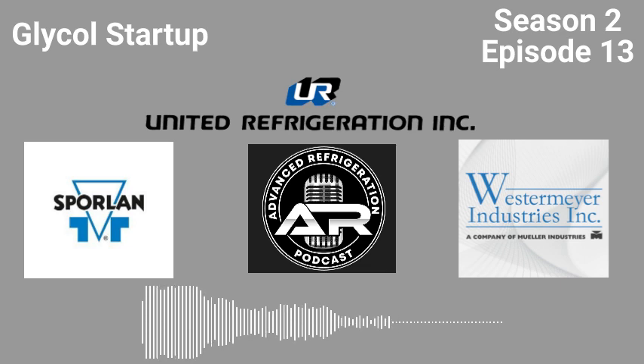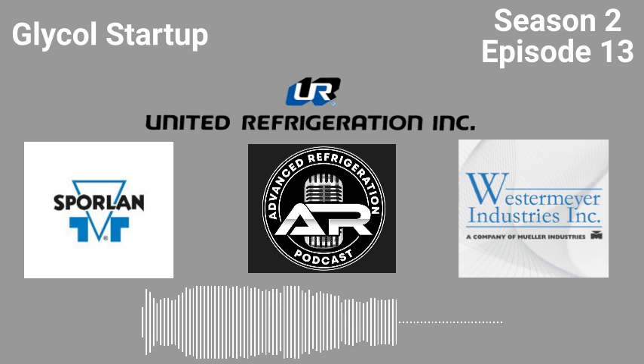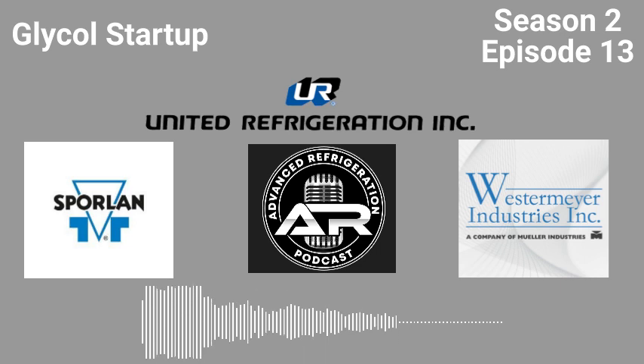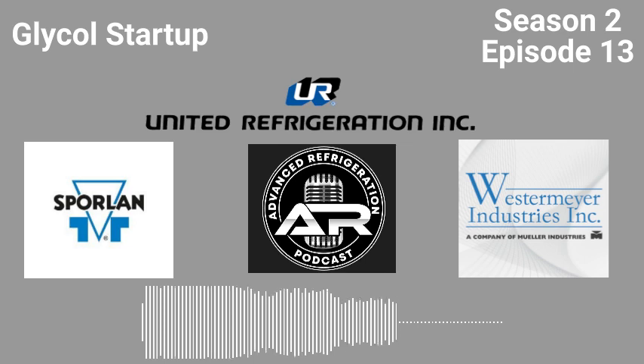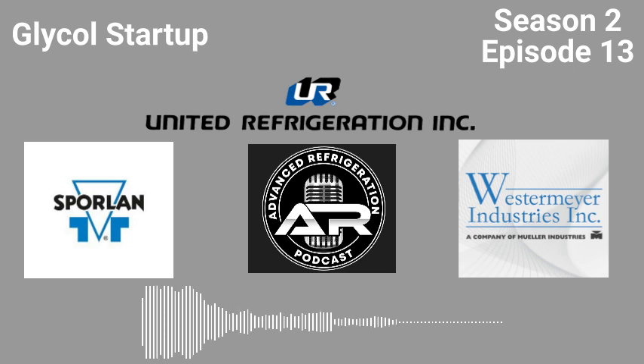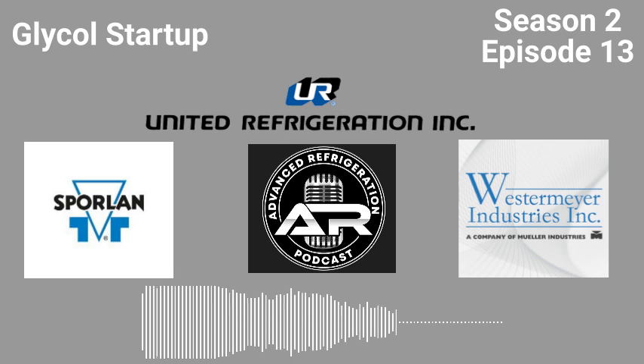The reason I don't like doing this is because you're putting water in the system no matter what, and it's untreated. Depending on how hard the water is, now you have a bunch of minerals in there, and it could lead to scaling issues later. So that's a big reason I'm not a big fan of it. But in the same sense, you have to follow their guide, and you want to get as much of the crap out as you can. To be honest, I never really see the water dirty, but it's more for me to make sure there are no leaks and everything else is good with the system.